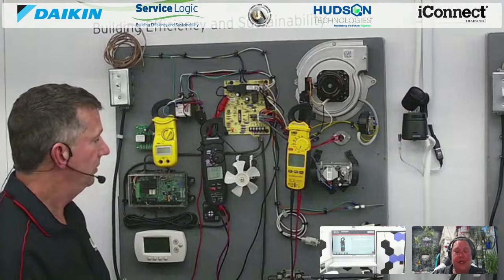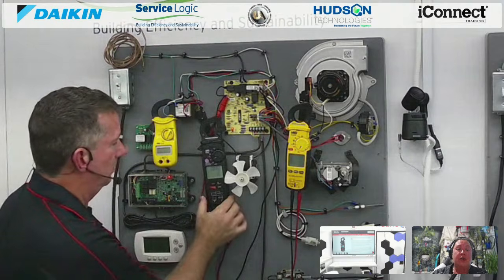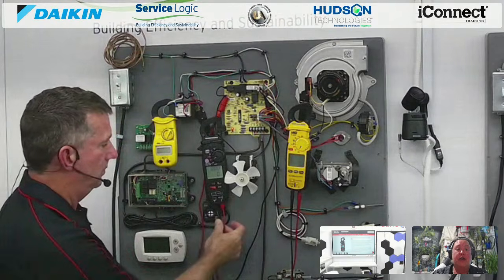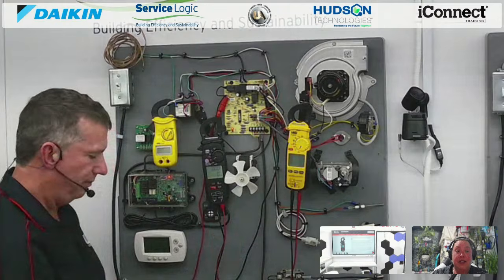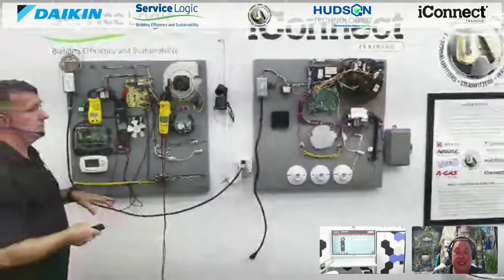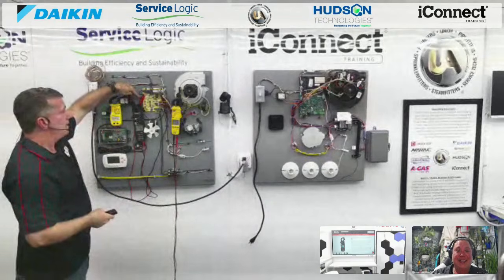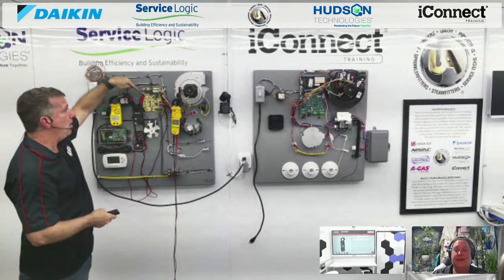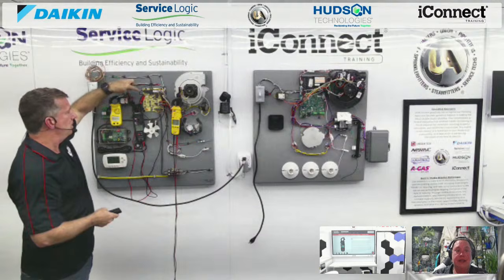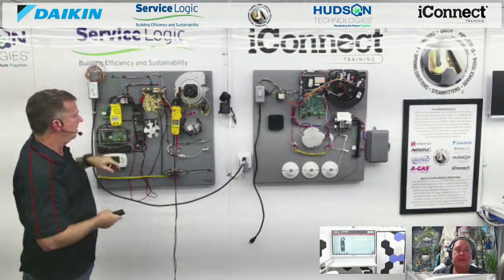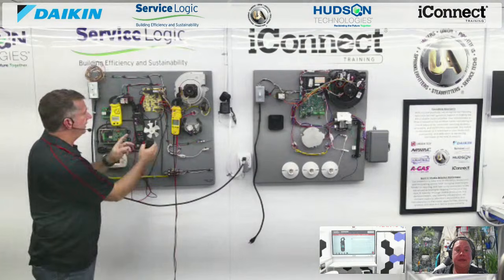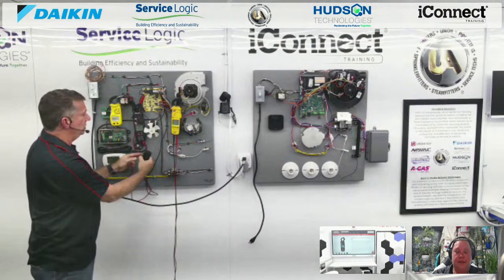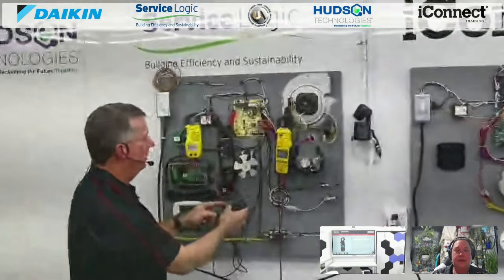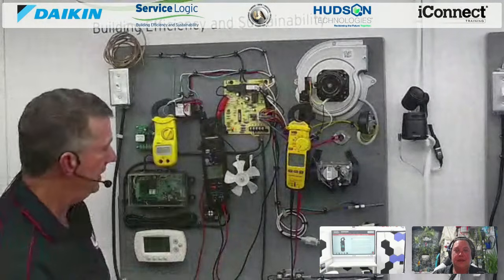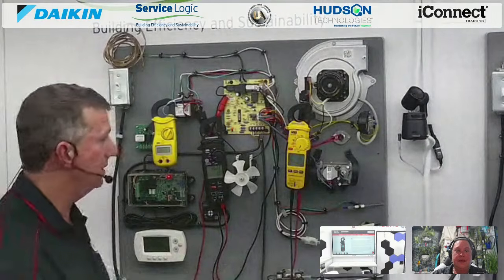And then we're also going to want to be able to test our volts at the same time, with your test leads. For this scenario, I've gone back to my main board, and the two power wires for our fan motor are right here on the fan's tap and then over on common. So these two leads I have connected on - we're reading voltage here and we're reading amperage here. As you can see right now, we're not reading anything at all.